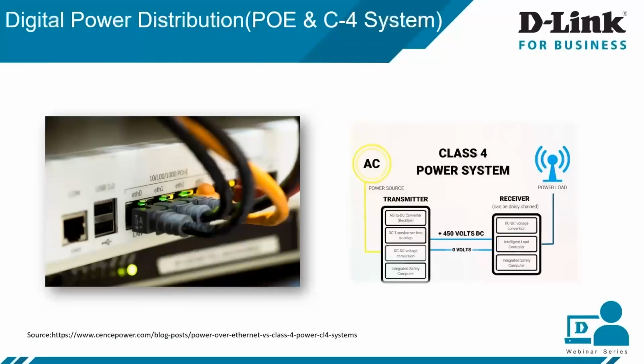Another major difference is that PoE provides both power and data through a single cable, the convergence of data and power we know in PoE, thus reducing the number of wires or raw material used in the building. But all this also depends on the quality of structured cabling, whether we are using pure copper, and which category of cable we are using. Depending on wire gauge, the number of cables in the bundle impacts insertion loss. Even if the operating temperature of the cable is not proper, it degrades the cable due to heat generation in the bundle cable. So structured cabling's role is very vital.